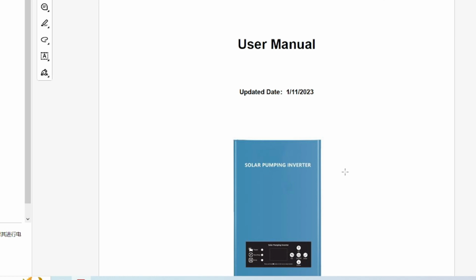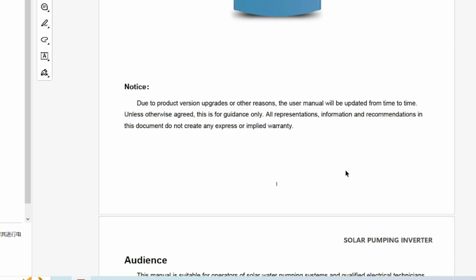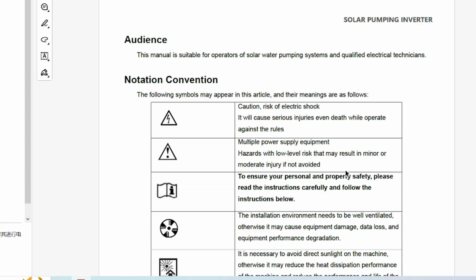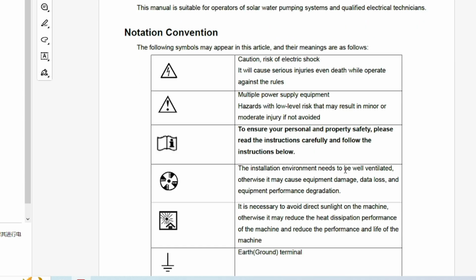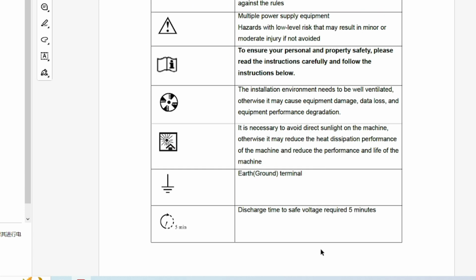This is the solar pump inverter user manual. Before we operate the inverter, we need to check the user manual. This inverter has capacitors. You need to wait 5 minutes after you switch off the input breakers.